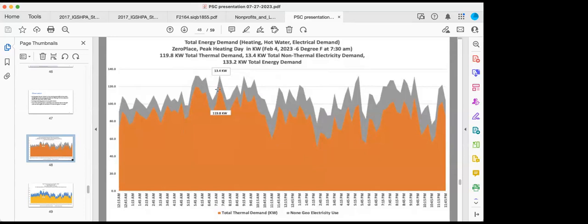And the trick is to say, okay, how do we satisfy all this? There's another interesting implication here: look at how the loop field reacts during the day to an increased energy demand of the building. It essentially lowers during the day, but at peak time it actually increases its capacity or contribution. So while it's not dispatchable, it acts like one. At the highest energy use, it releases the most energy.